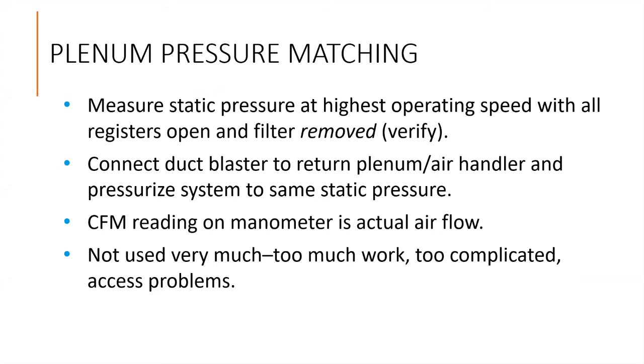Plenum pressure matching uses a duct blaster to match normal operating system static pressure. First, measure the static pressure at its highest operating speed with all the registers open and the filter removed. Then turn it off, connect the duct blaster to the return plenum, and pressurize the system to the same static pressure. The CFM reading on the manometer is the actual airflow. This technique is not used very much — most people consider it a little too much work or too complicated, and sometimes there can be access issues.